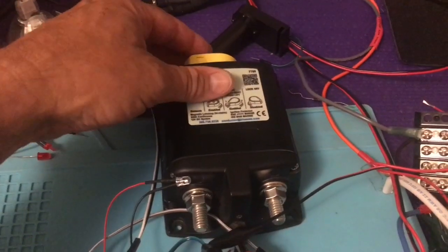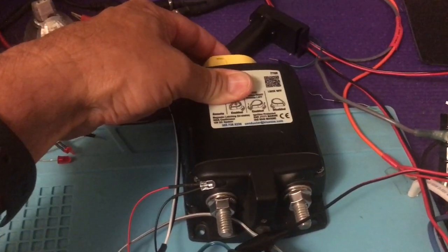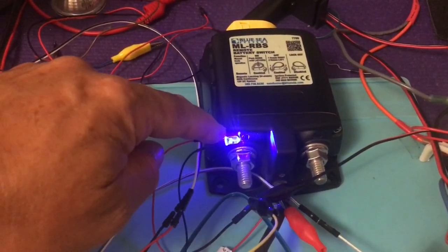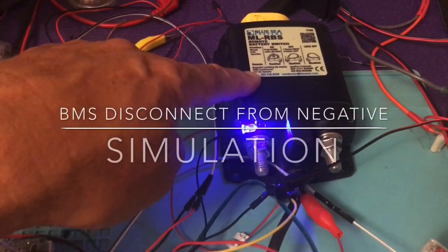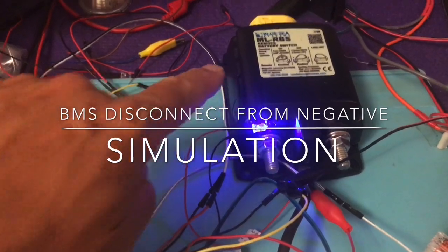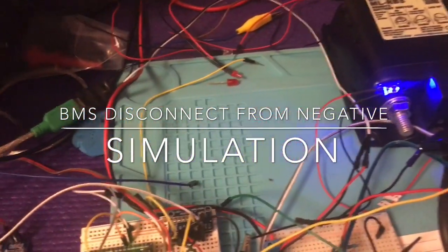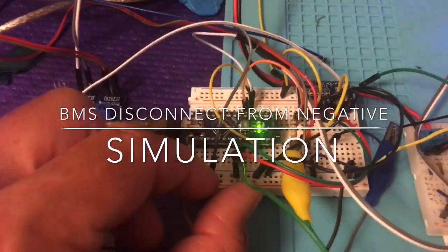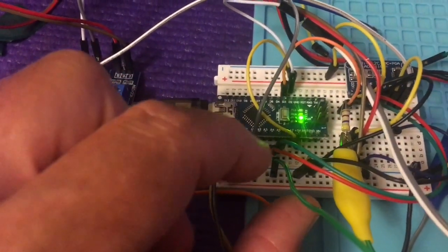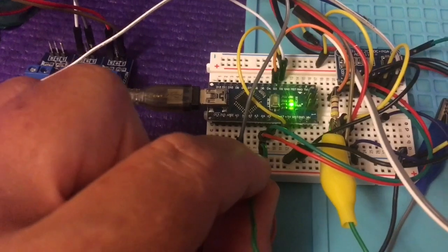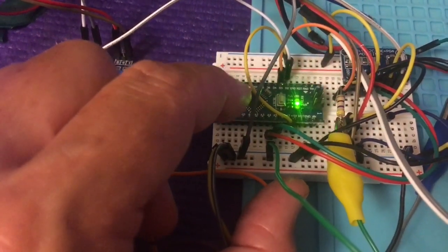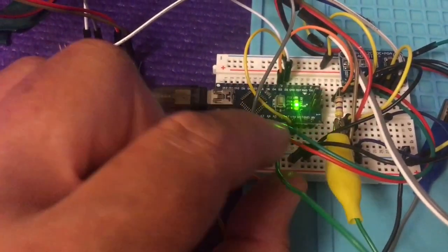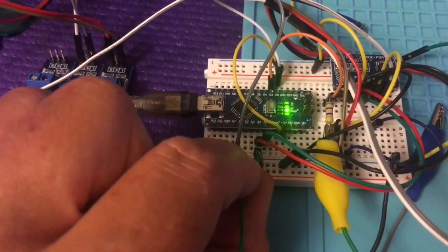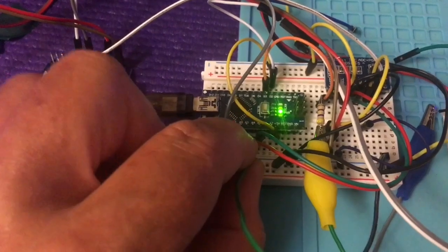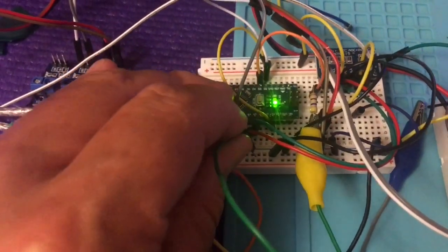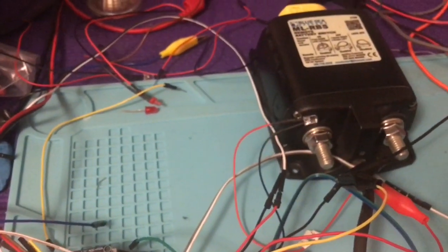In this test, I'm going to simulate a situation where the BMS is going to float the signal. So I've closed the relay again, and I'm going to simulate a situation where the BMS floats the signal. I'm feeding in a ground signal, using a pull-up resistor internal to this microprocessor's software, and I'm just going to simulate the floating of a signal from the BMS. So I'm just going to pull this pin from ground right now, and it fired and there's no blue light there.